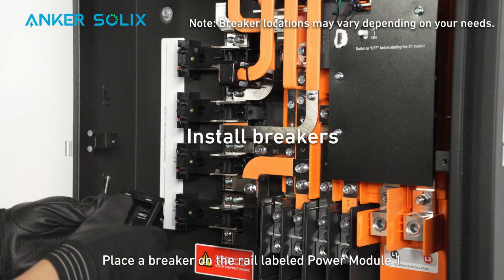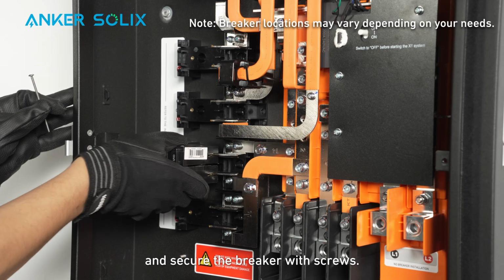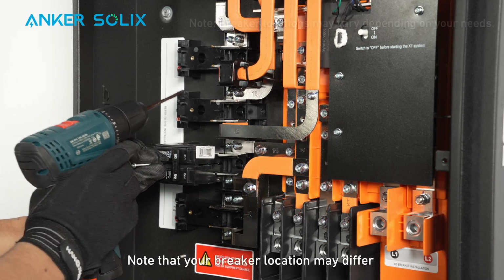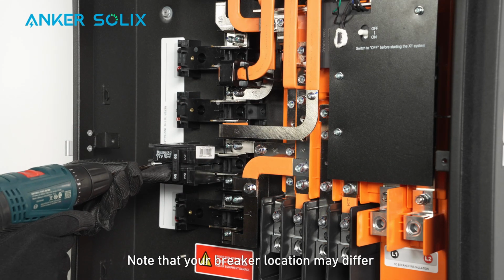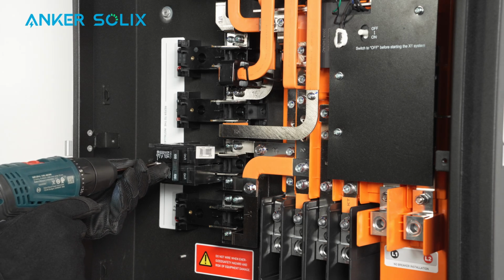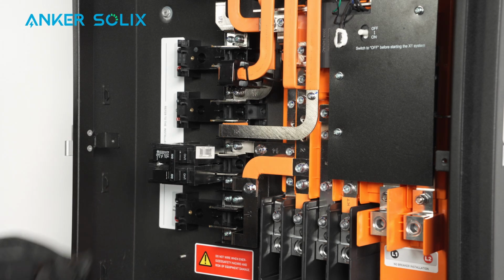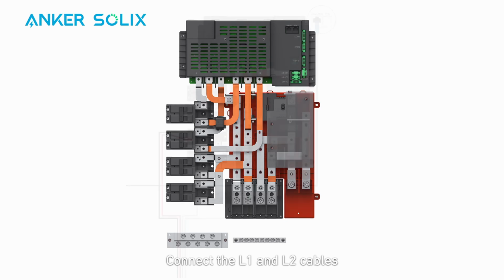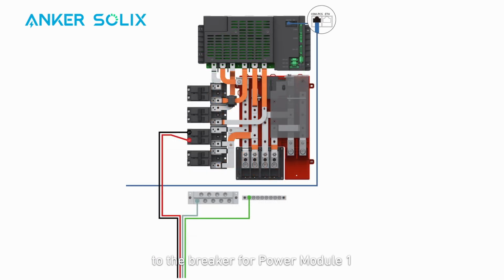Place a breaker on the rail labeled Power Module 1 and secure the breaker with screws. Note that your breaker location may differ depending on your location and needs. Connect the L1 and L2 cables to the breaker for Power Module 1. Install the neutral and ground cables to their respective wiring bars. Plug the RJ45 connector into the COM PCS port in the wiring compartment.